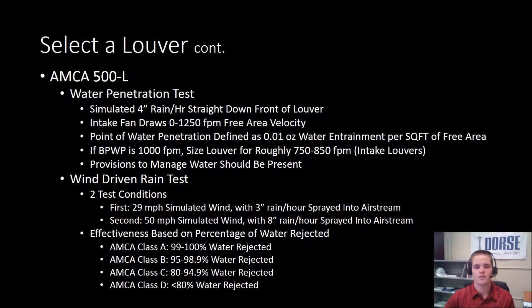Before we dive into how to select a louver, I want to cover AMCA 500L briefly. There are two tests in AMCA 500L that are important to what type of louver you want to select. The water penetration test simulates 4 inches of rain per hour being poured down the front of the louver in sheets, while an intake fan pulls air through the louver between 0 and 1250 feet per minute free area velocity. The point of water penetration is defined as 0.01 ounces of water being entrained in the airstream and making it through the louver per square foot of free area. A good rule of thumb for sizing louvers for this test: if the beginning point of water penetration, or BPWP, is 1000 feet per minute, then you will want to size the louver for roughly 750 to 850 feet per minute free area velocity.